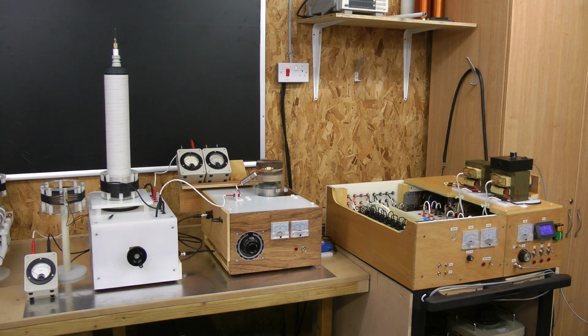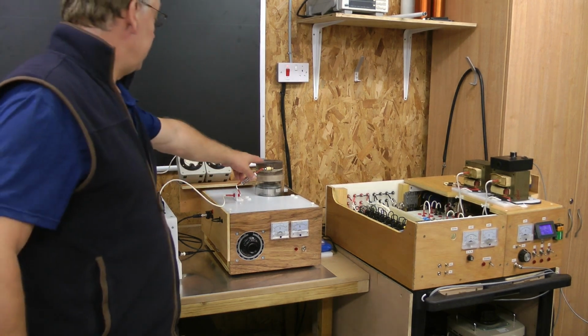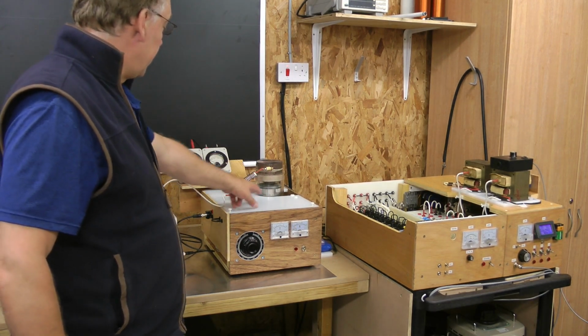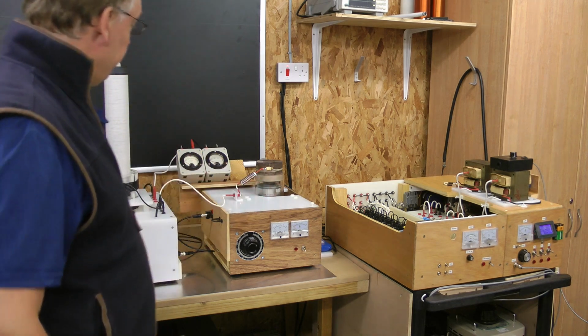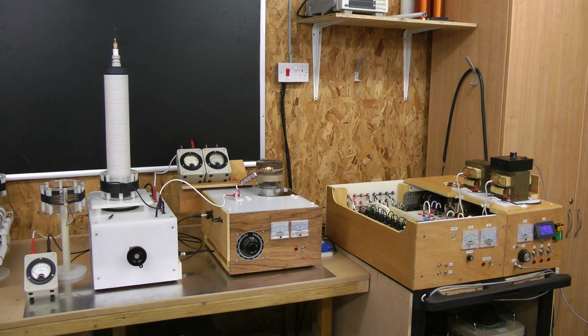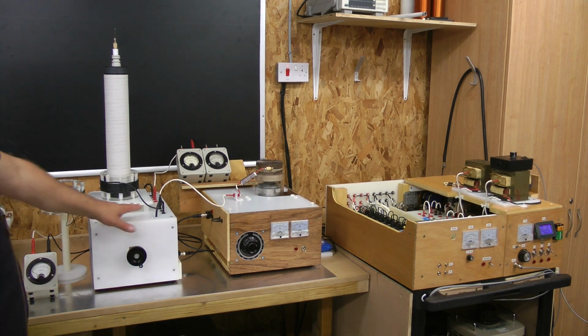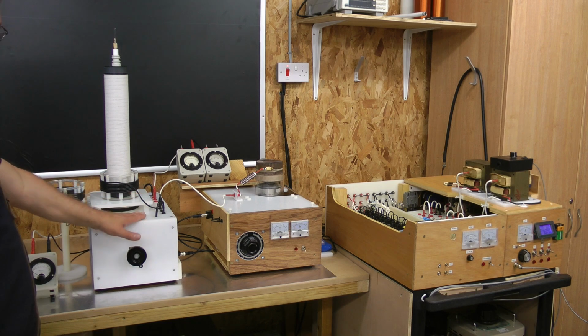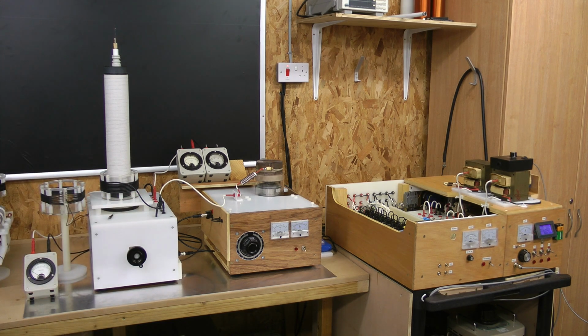In the middle we've got the GU5B generator, used here as a power oscillator. We can see the GU5B at the top, this is the anode, with the anode connection and cooling chimney, and I'll go into more detail on the changes there. Then there's the tube unit, the coil unit, which has the big vacuum variable tuning capacitor underneath.